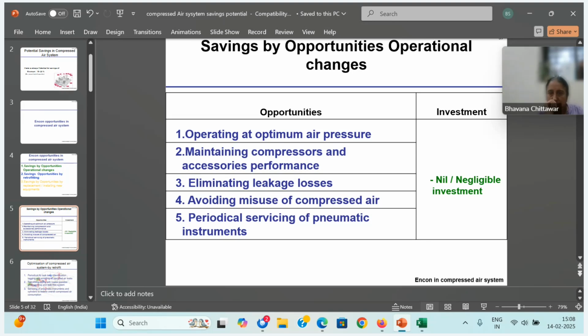You have to check the performance of compressors always. You have to check specific power consumption, or parameters like DP across the air filter. Nowadays, I'm concentrating on screw compressors because the majority of industries have switched over to screw compressors. Reciprocating compressors are only very limited, only for high pressure and gas applications. So I'm concentrating more on screw compressors. Of course, if anybody is interested in reciprocating compressors, I can cover that also, because all my earlier presentations were for reciprocating compressors only. Of late I switched over, because many clients, almost more than 90%, switched over to screw compressors for some reason or other.